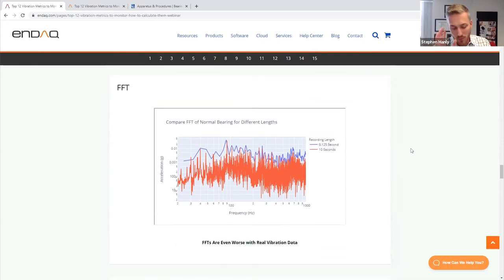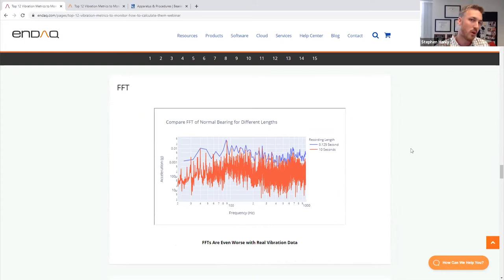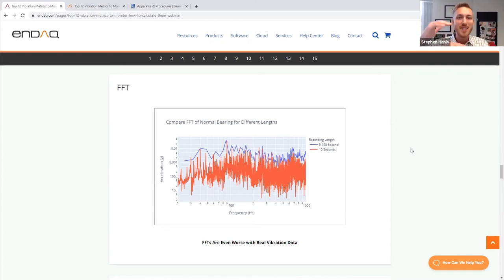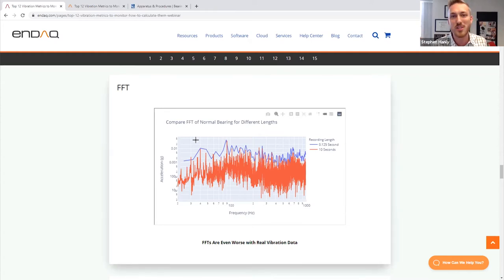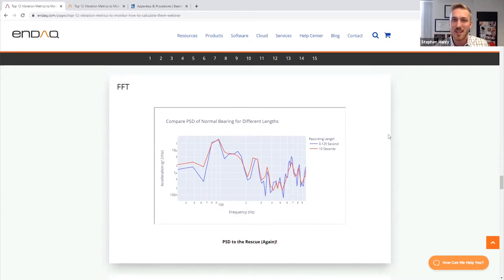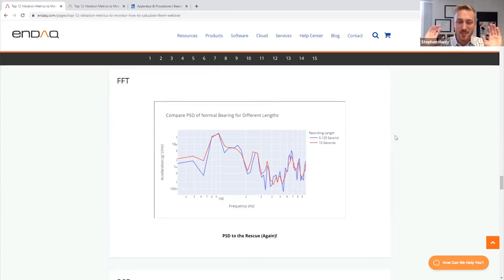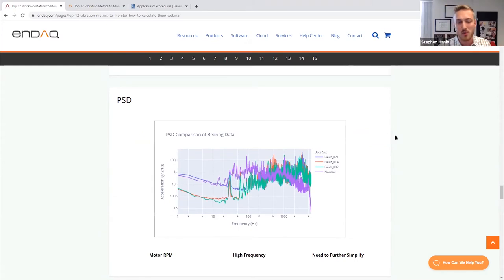Before focusing on the PSD, let's put the FFT to rest. Looking at the actual bearing data, comparing an FFT calculated off the full 10 seconds versus just a tenth of a second, the order of magnitude between the two FFTs is way different — you might incorrectly conclude one vibration profile is worse than the other, but they're the exact same profile. If you look at the PSD instead, they match up perfectly. PSDs are how you properly quantify a vibration signal in the frequency domain.